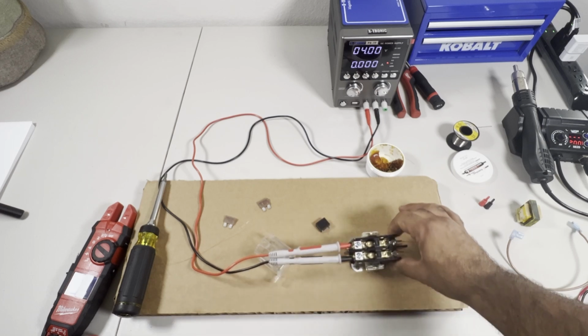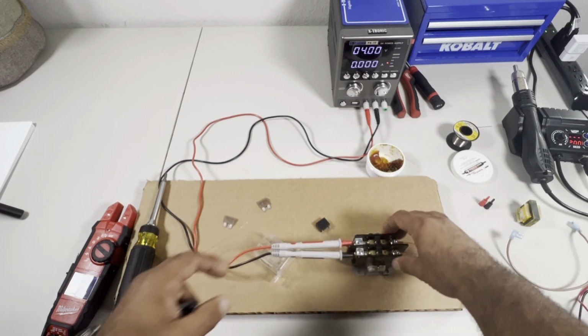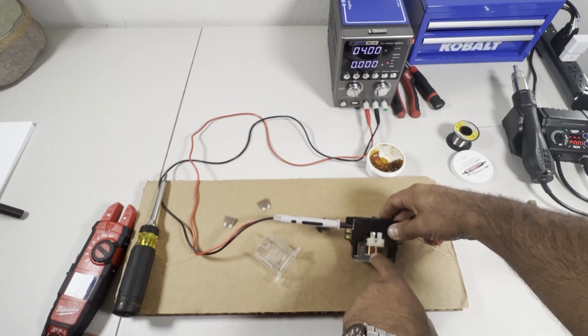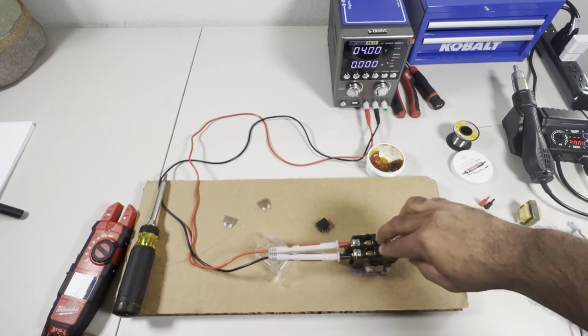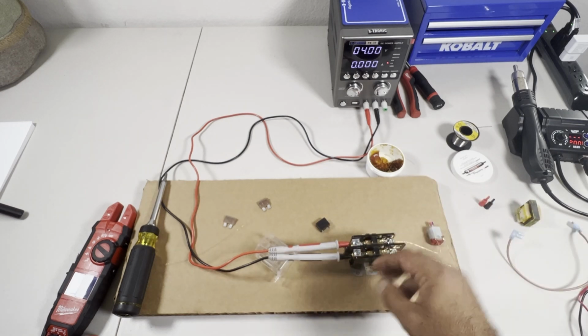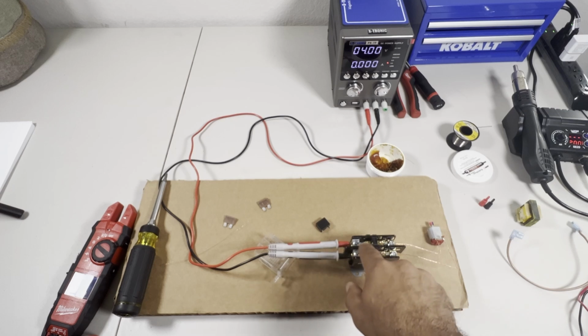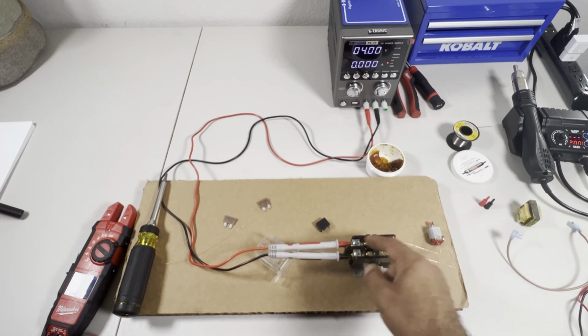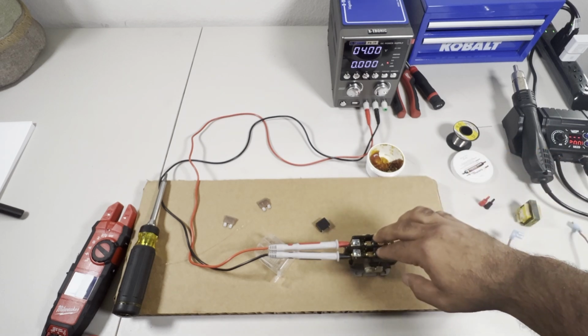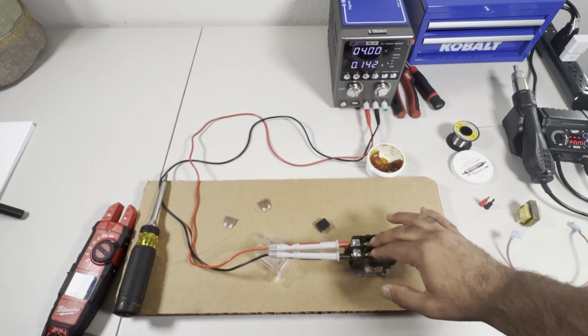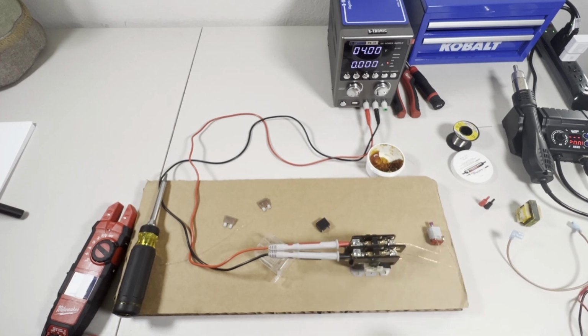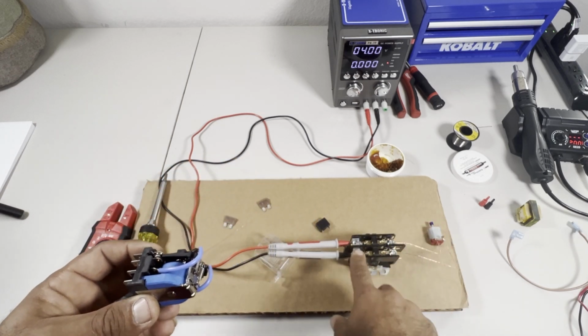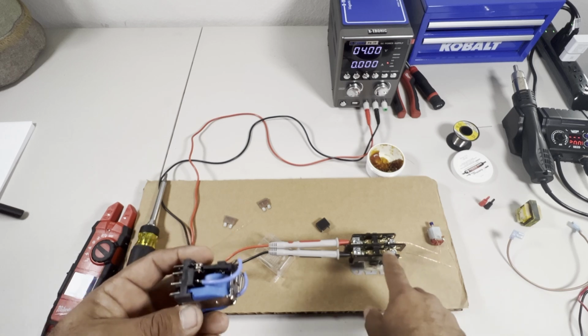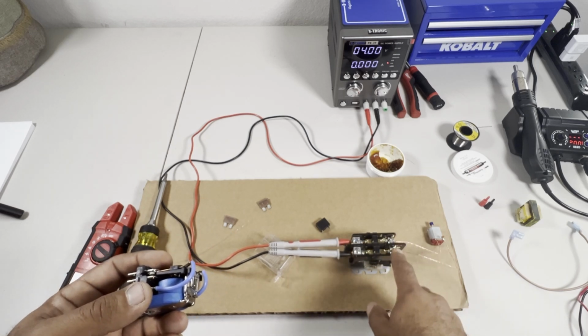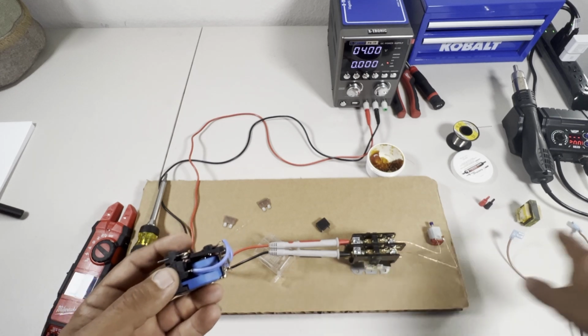And as soon as it has voltage to these parts, this coil that you see at the bottom is going to create a magnetic field which is going to pull down on these two at the same time. And when that happens, there is a bridge on the top that is going to let the electrons pass through. And that's what you're going to hear, a loud pop every time this relay comes on and your load is running. And when it stops, the motor will stop. This one is a double throw, single pole type relay. There are two inputs, two outputs, but there is only one pole required for the power to go in.